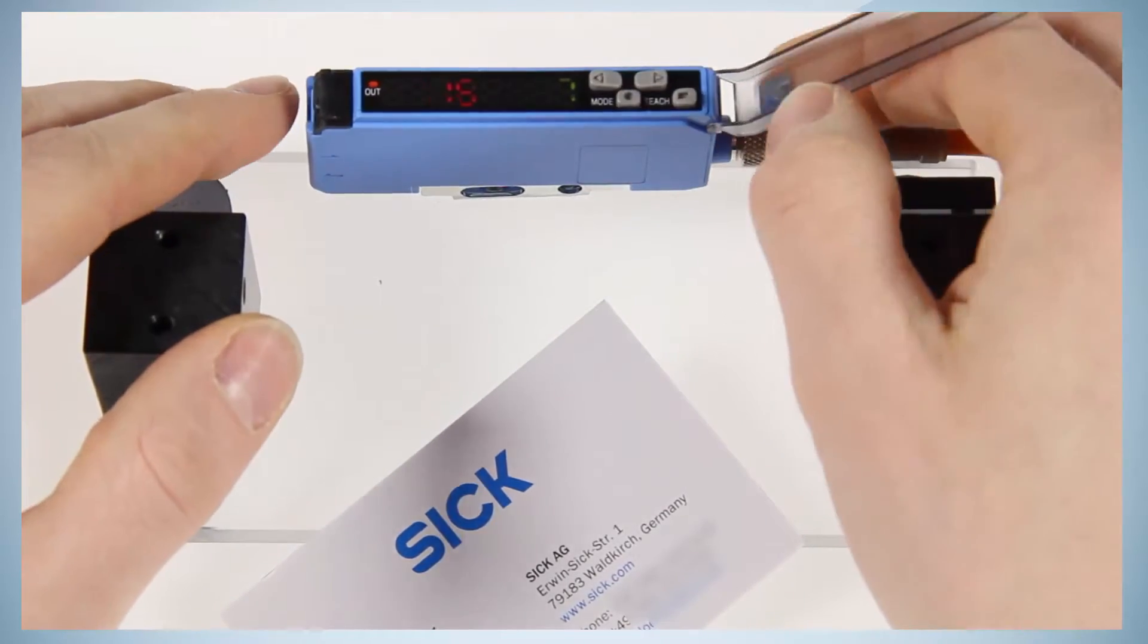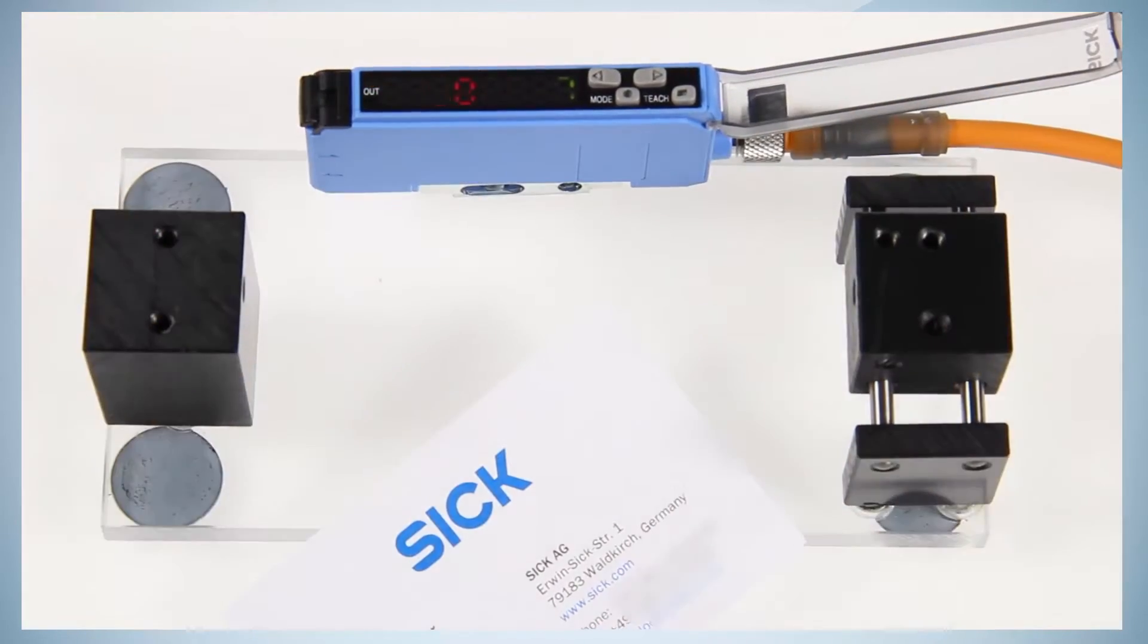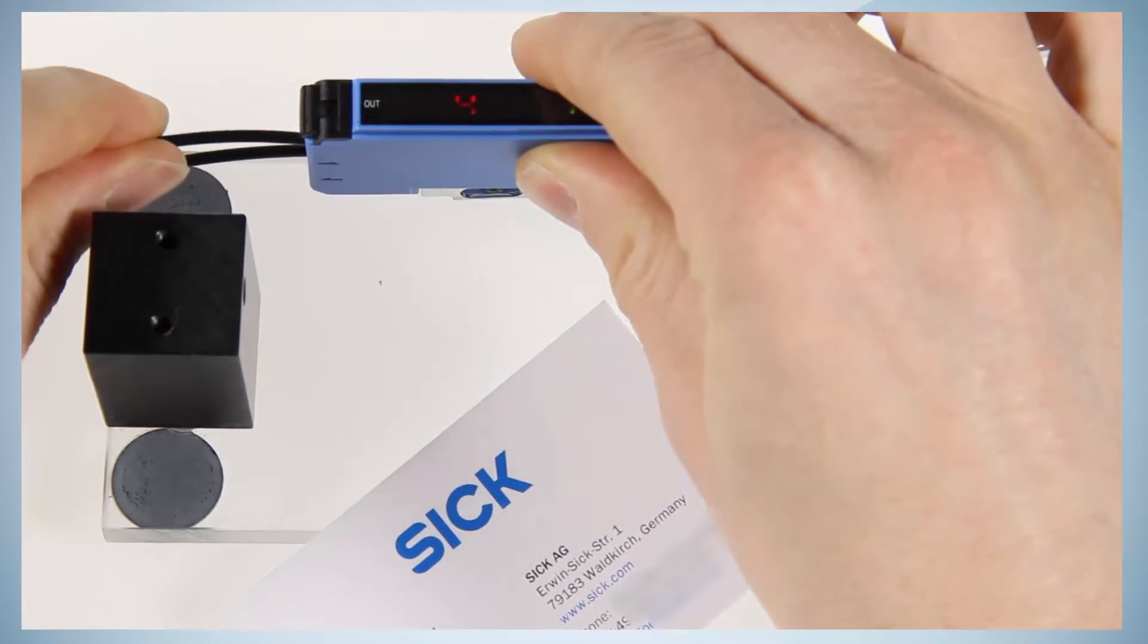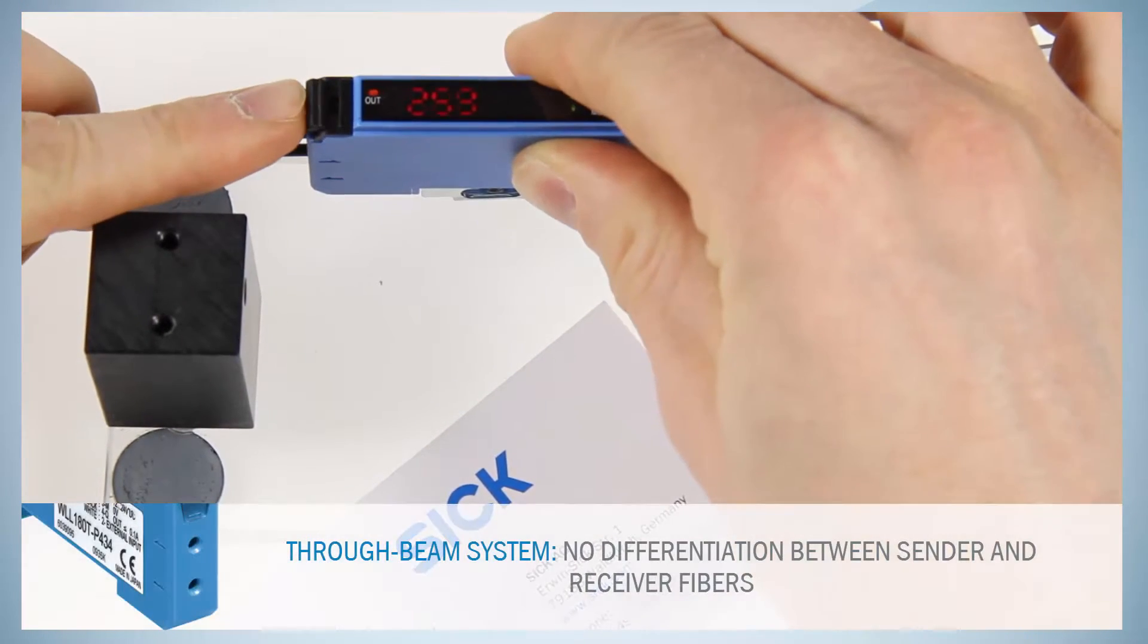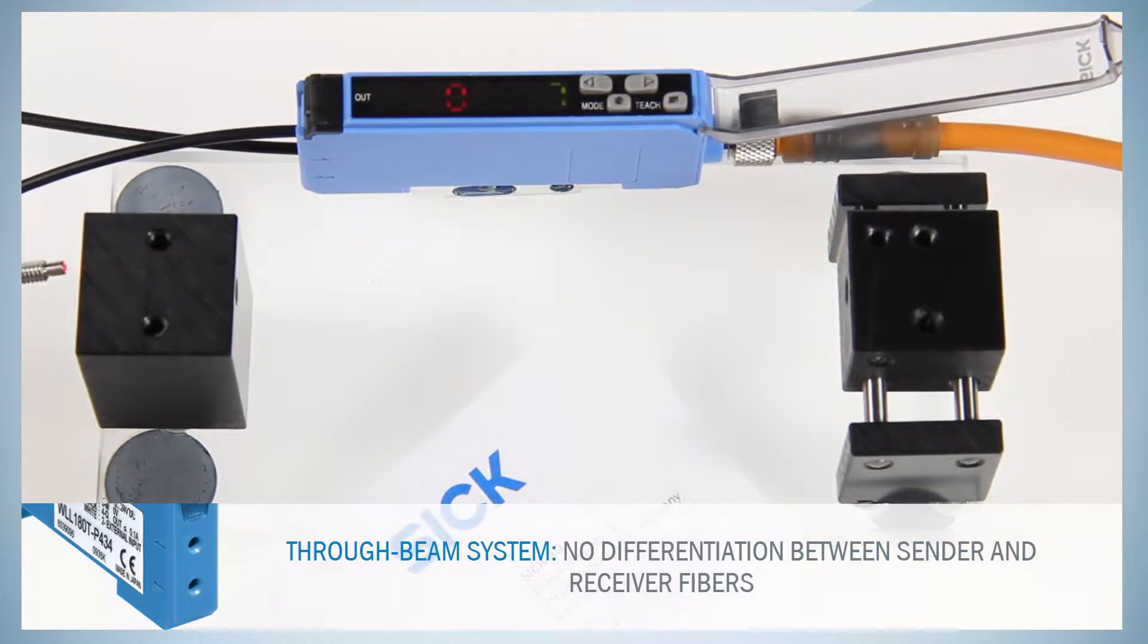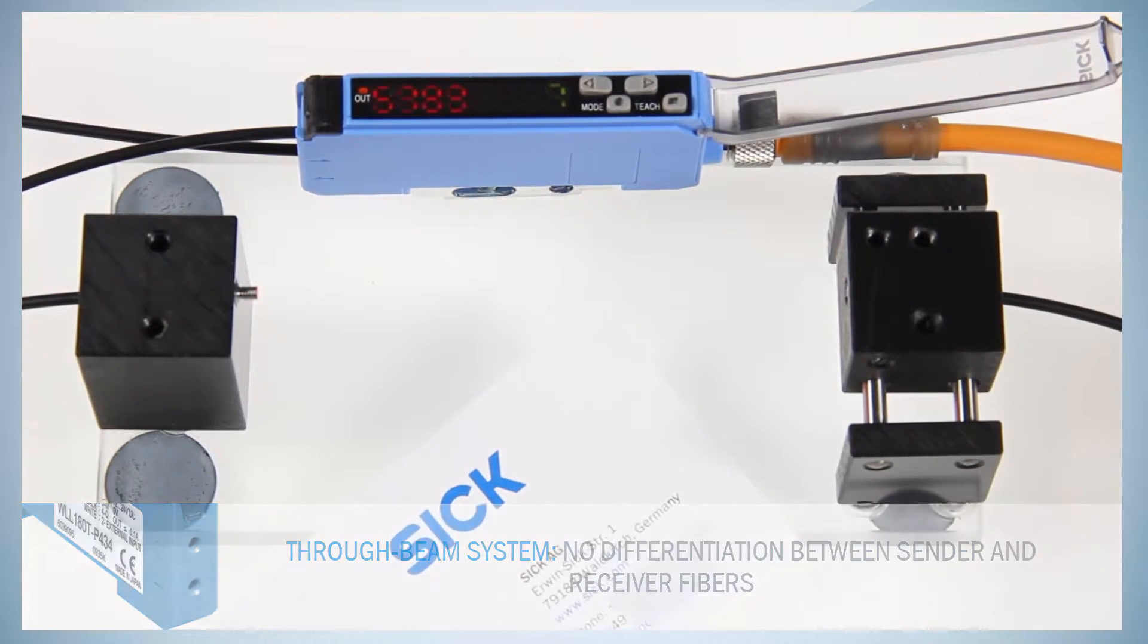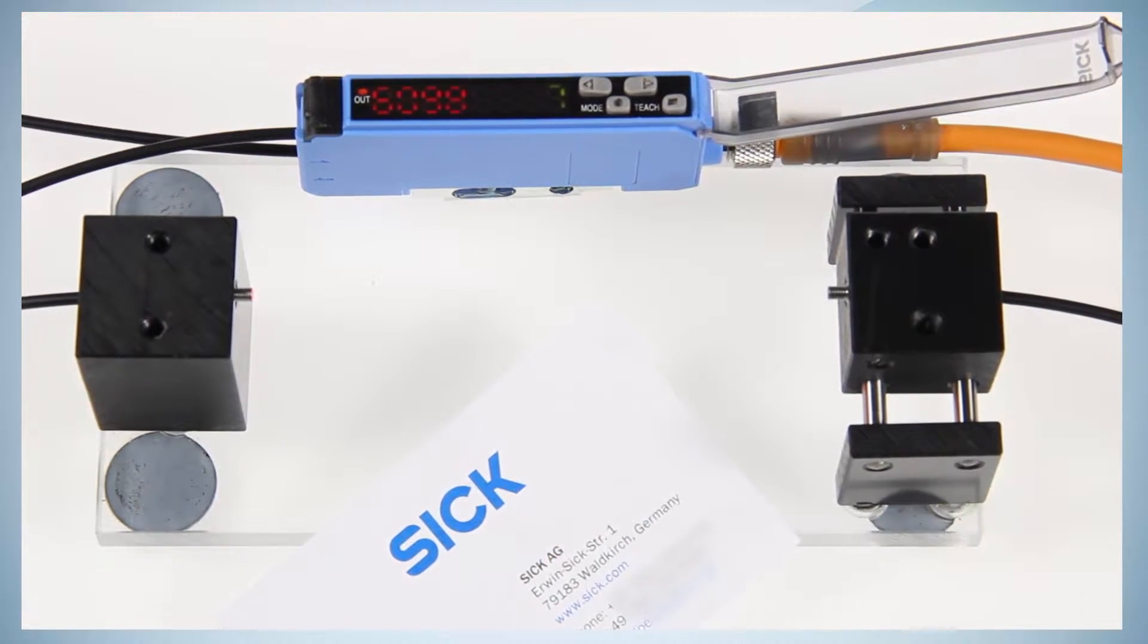Open the transparent plastic cover of the amplifier and open the lock lever by pushing it downwards. Insert the fiber cables in the connection openings of the amplifier till the stop and lock them by pushing the lock lever upwards. Mount the fiber heads of the LL3TB01 in the cubic supports of the demo kit.